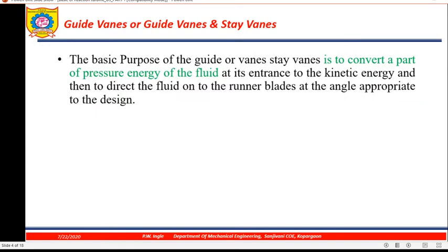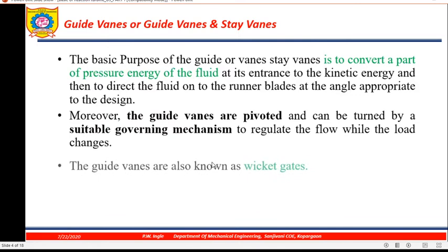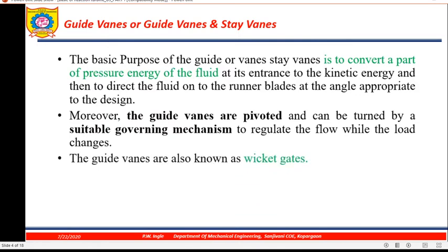Third one is guide vanes, or guide vanes and stay vanes. The basic purpose of guide vanes or stay vanes is to convert a part of pressure energy at its entrance into kinetic energy, and then to direct the fluid onto the runner blade at an angle appropriate to the design. The guide vanes are pivoted, so I told you that they are movable, and can be moved by a suitable governing mechanism to regulate the flow while the load changes.